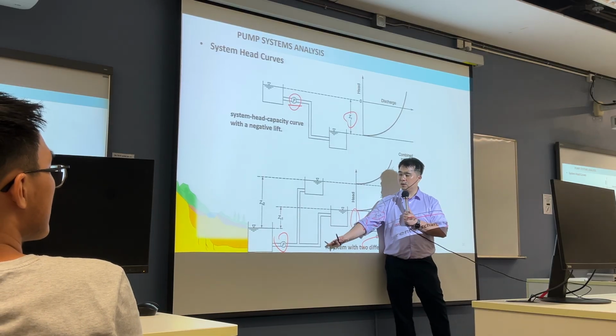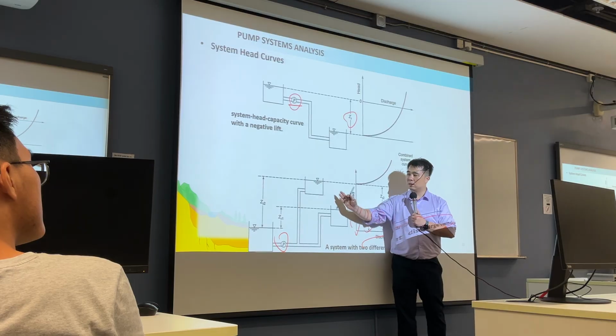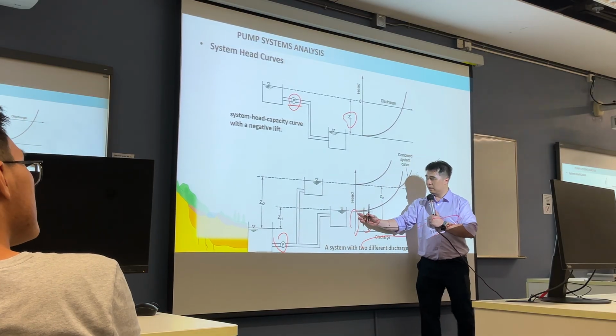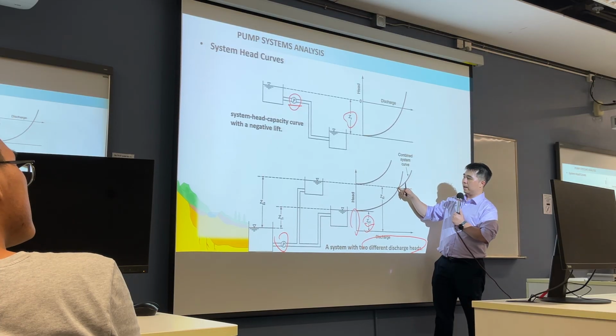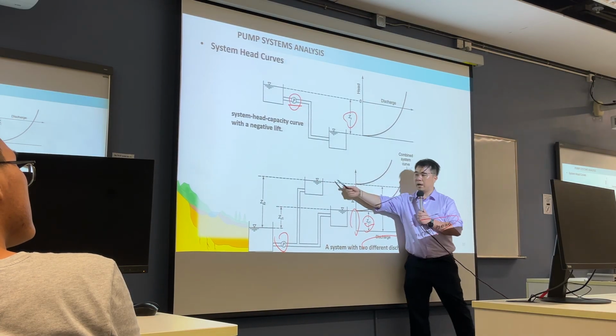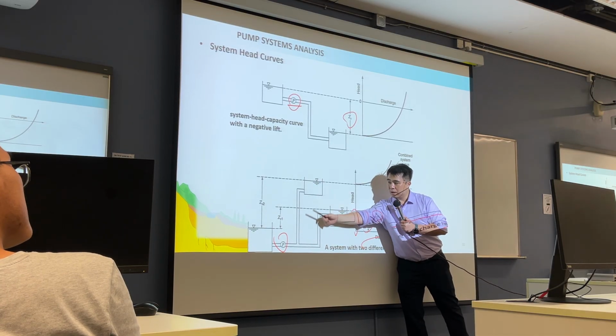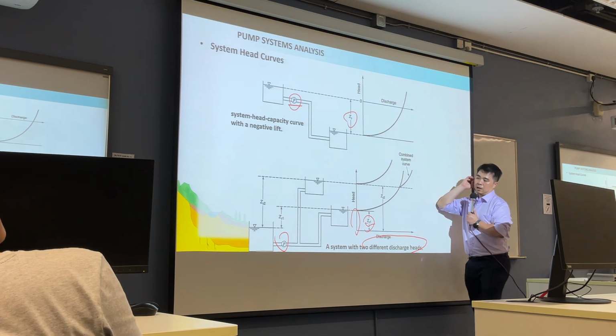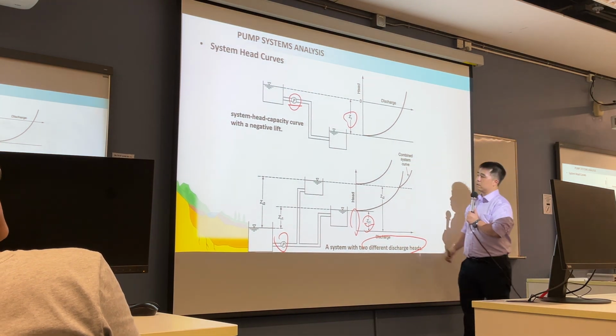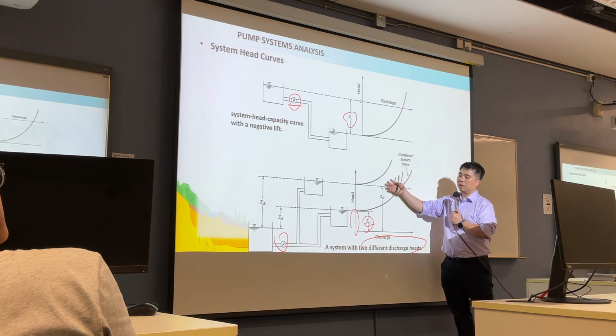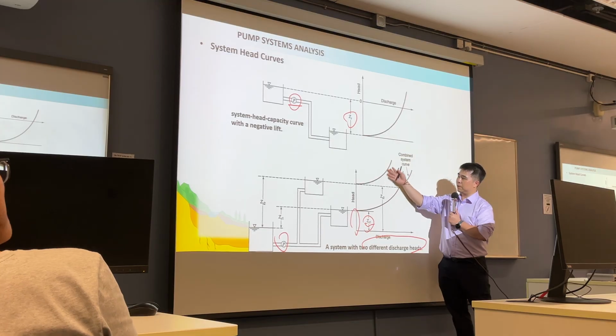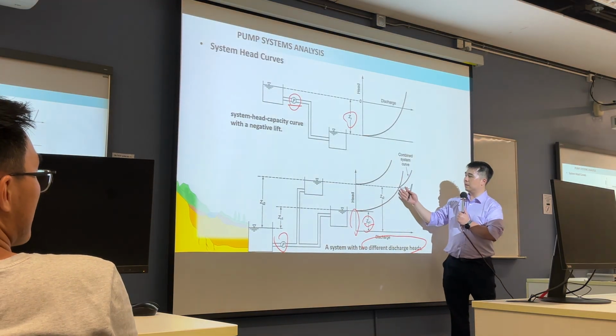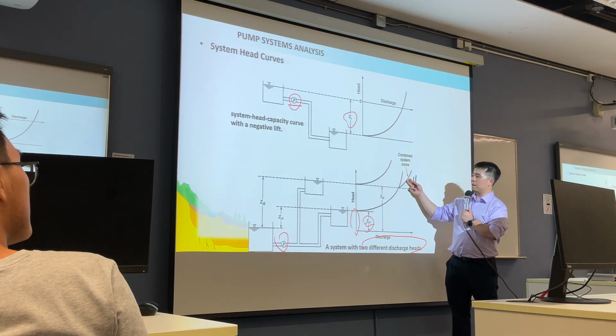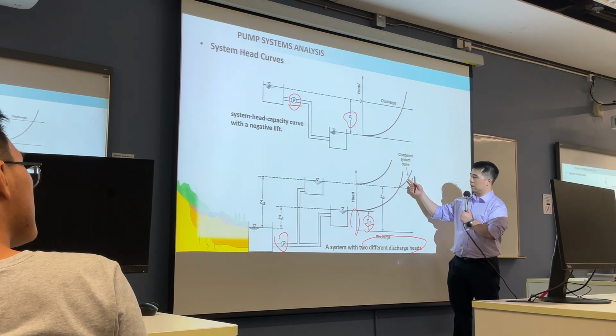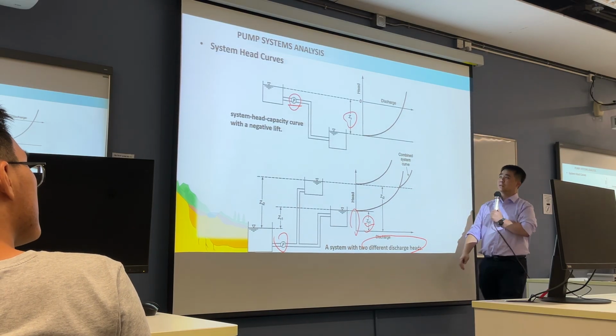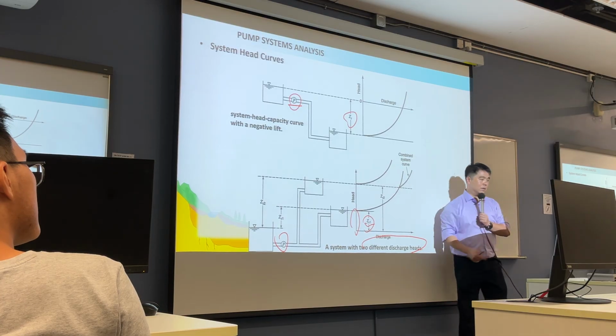But if you want to pump water to both reservoirs at the same time, you need to at least provide a pump head as large as here, to overcome the head difference between the second receiving reservoir and the source reservoir, okay. So there is this two receiving reservoir situation, okay. If that happens, the same head profile can have the additional discharge. You will have this kind of system requirement, okay.